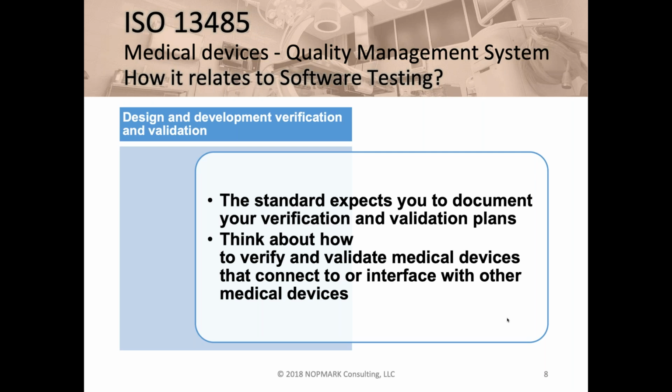Another interesting item called out within this standard for software testing is that it's asking you to not only think about, but also verify and perform your testing of your medical device software as it connects to or interfaces with other medical device software.